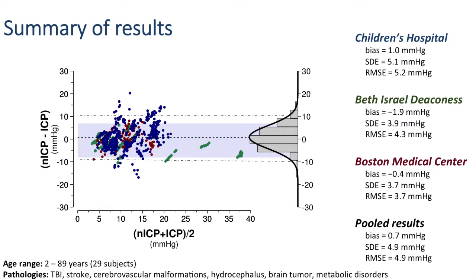So what if we analyze our results? The baseline model is the model that I've just shown. A bias of 0.5 to 0.7 millimeters of mercury, SDE of 5 millimeters of mercury, with a root mean squared error of 5 millimeters of mercury. If we don't correct for the hematocrit, the density dependence of the hematocrit, these performance metrics essentially don't change. Whether you're at 0.5 or 0.8, there's nothing that is statistically significant here. So what we were able to show is that taking care of the hematocrit correction for the blood density doesn't really change anything, at least over the range that we've seen in our data.